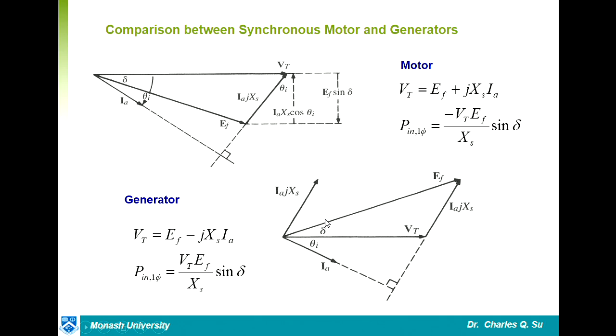Torque angle and power angle are different things, right? Power angle is the angle between your voltage and the current. It depends on the positive or negative power angle. Your load, your supply, can be capacitive or inductive. So with this energization of the DC magnetic field, your torque angle can change, and your power angle especially can change. You can go negative, or you can go positive. Your current can go this way. So if your current is leading ahead of voltage, you would produce reactive power. Sorry, for the generator side, you would consume reactive power. In this case, your current is lagging behind the voltage. For a generator, you produce reactive power.